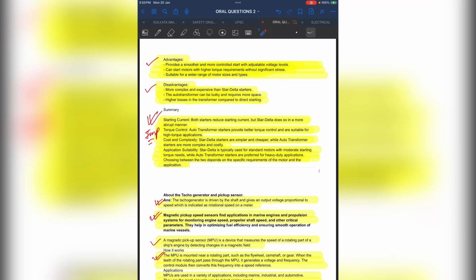And what are the disadvantages? It is more complex and expensive. The auto transformer is a more expensive and more complex system than star delta. The auto transformer can be bulky and requires more space. More space is required for the auto transformer. There is also higher loss in the transformer compared to direct starting.